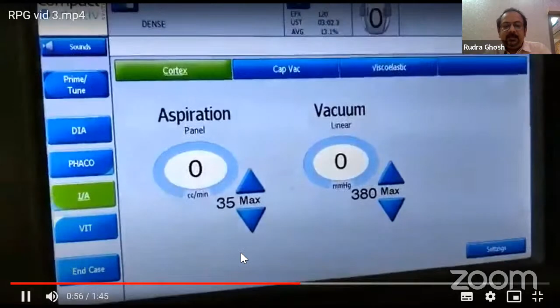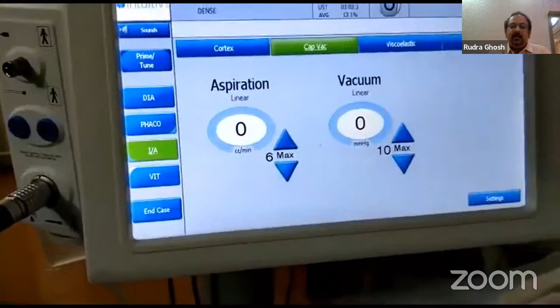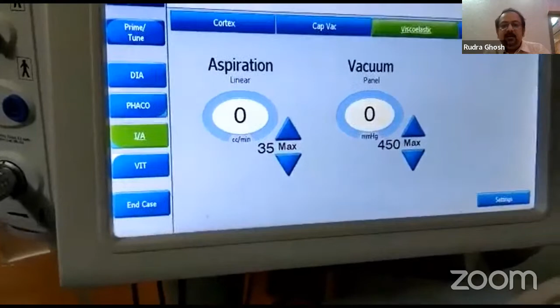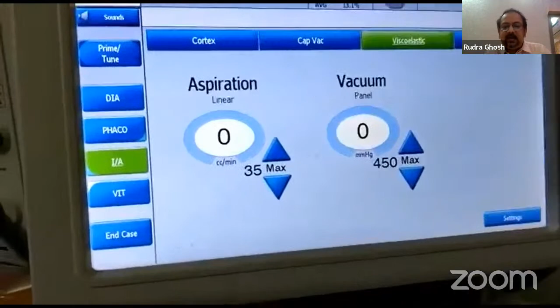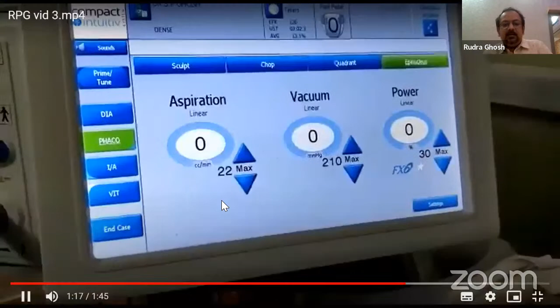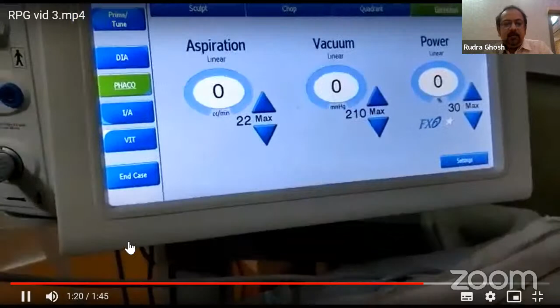For example, here I have set the aspiration and vacuum to 35 and 380. But in CapVac, you can see they are all lowered. Aspiration is 6 and vacuum is 10, for example. And for taking out the viscoelastics, here it's set to 35 and 450. Now I will show the change of the panel with the change of my foot switch.